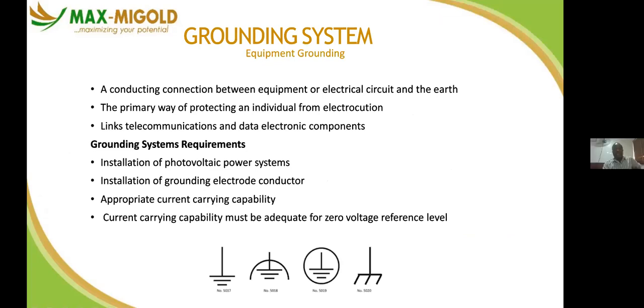Yes, sir. Okay, I said earthing is the process of connecting all your installation to the ground through a copper rod or earth pit. And there are materials that enhance earth conductivity. One of such is the electrolyte. Most of you use salt. That's an electrolyte in the form of liquid also. So salt allows the passage of electricity easily. So when you pour that salt around your earth pit, it lowers the resistance of that earth.